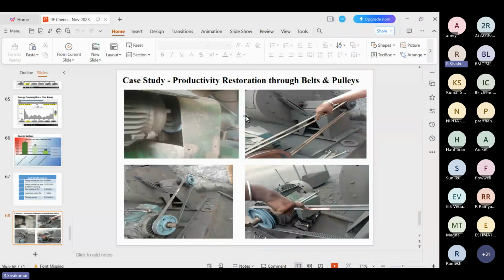During our visit, we saw that slippage is more due to more cuts in the belt, so the motor output, the mechanical power, is not properly transmitted from the motor to the blower driven by this old belt. Because of this old belt, the pulleys are worn out, and the belt is also cut at a lot of edges, so it was wobbling more. The slippage is high.